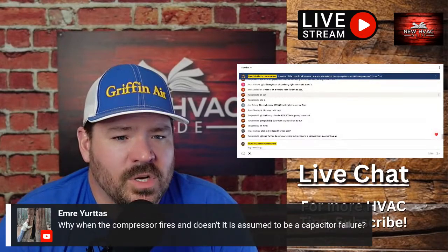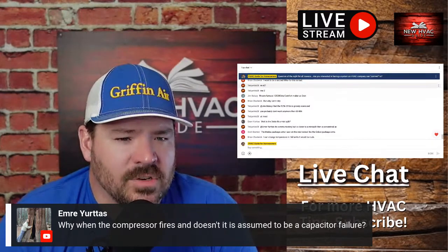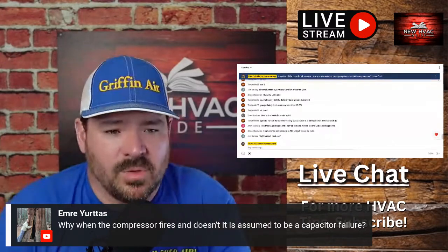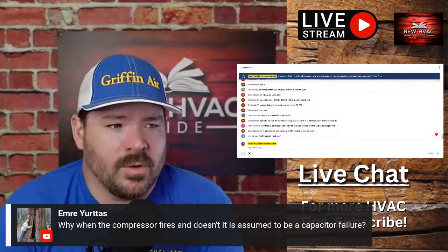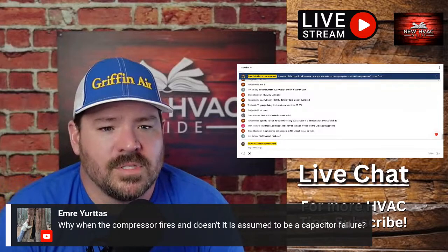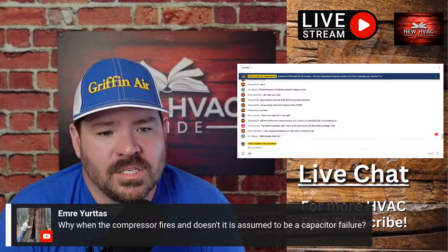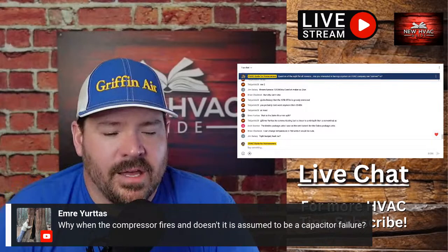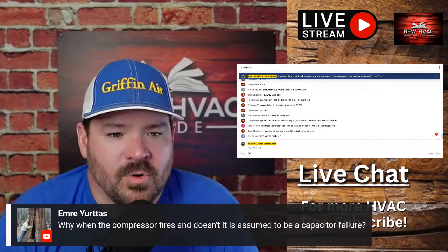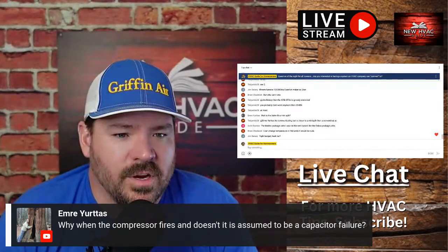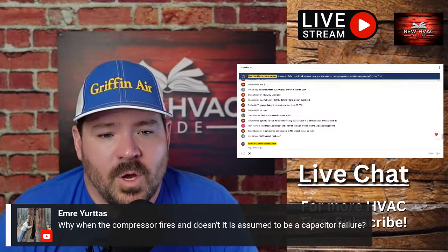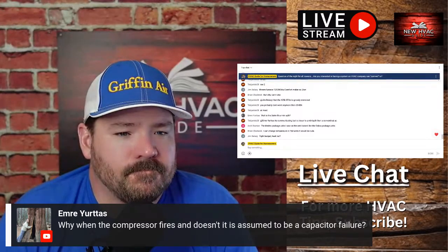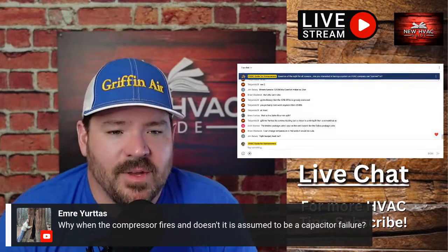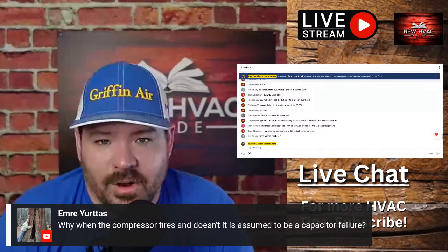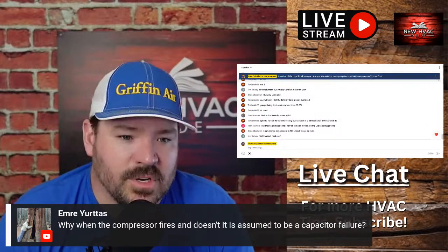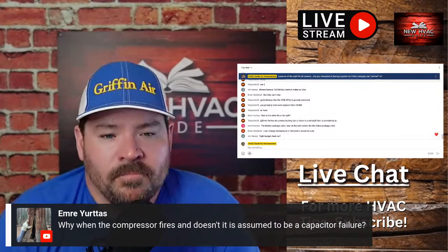Emery asks, why when the compressor fires and it doesn't run, is it assumed to be capacitor failure? Well, it's not always the capacitor, it just depends on what the problem is. The capacitor is meant to get that system on and running — it absorbs the initial spike in resistance as the system turns on, which is why the amps increase, and the capacitor helps the system get up and rolling. But it doesn't always mean the capacitor has failed. There are other reasons too, such as a problem with the compressor itself, though there's not a lot else there. If it's receiving power, that's part of it — is the board or contactor sending voltage to it properly? But if all that's working correctly, the capacitor is really the only other component there.